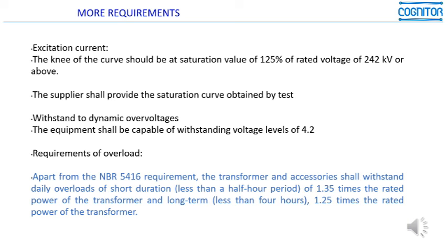Then this is of course a very important specification for a transformer to define the saturation values, because the power utility needed to attend the requirements established by the electrical sector regulator related to the values of maximum saturation permitted.